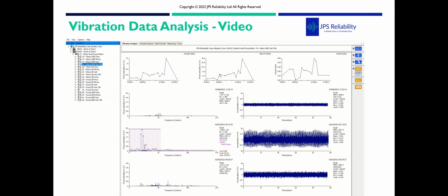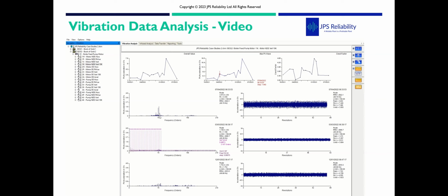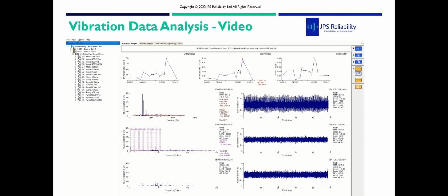You can see we started to have some electrical activity around then. Let's change that to hertz. There we go. You can see even back months, well, years ago, we were getting around 2 times the drive frequency pulse from the drive. So we've always been having some electrical activity. We knew there was something occurring, but gradually over time it increased, got higher and higher. Impact has started to come in. And then just before discussion of the planned outage, it went up quite high. So now the risk is really high. We cannot push this asset any further.